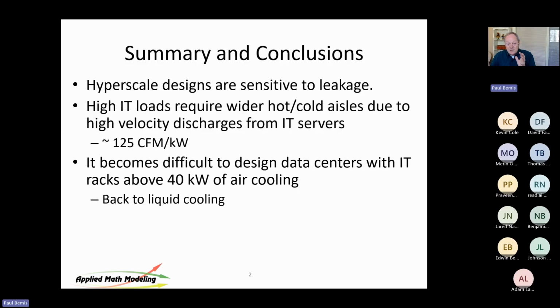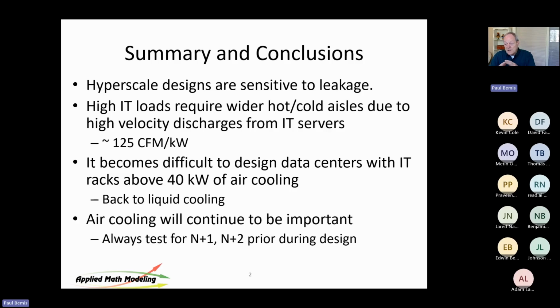Above 40 kilowatts for air, I mean, that's the upper limit. I've done some as high as 44 with air, but the problem we run into is there's just so much volume. You're trying to get so much volume into the room that it becomes problematic. Difficult to get really much above that, in my opinion. And always test N+1 and N+2 in various configurations.